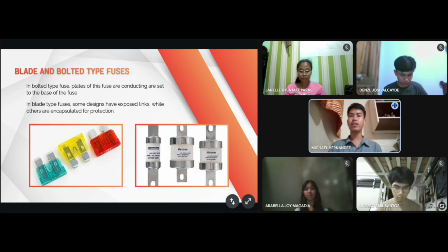On the other hand, a bolted type fuse is designed for higher current ratings and harsher environments. Instead of being pushed in, it is bolted securely into place to ensure a firm, vibration-resistant connection. This type is often found in industrial machinery and power distribution systems where reliability is critical. Both blade and bolted type fuses serve the same basic purpose: to protect electrical circuits by breaking the connection when too much current flows through. The main difference lies in how they are installed and the amount of current they can handle. Next slide.